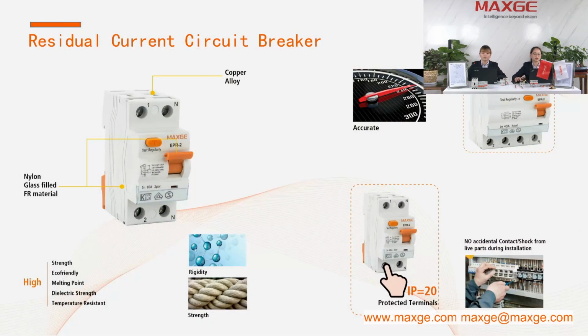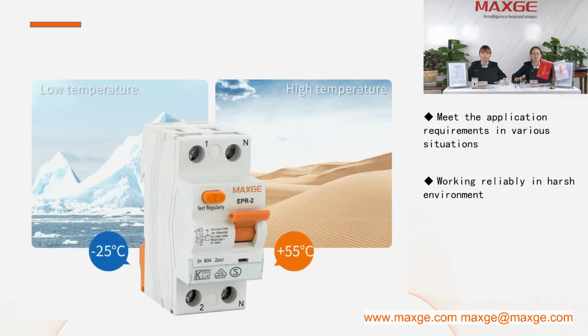Our RCCB is made with high quality plastic and metal parts. It is compliant with IP20 protection. IP20 means the electrician's finger cannot touch the live part while the RCCB works. Every design should consider safety standards. And our RCCB can work reliably in harsh environments. The low temperature is -25 degrees and the high temperature is 55 degrees. It meets the application requirements in various situations.